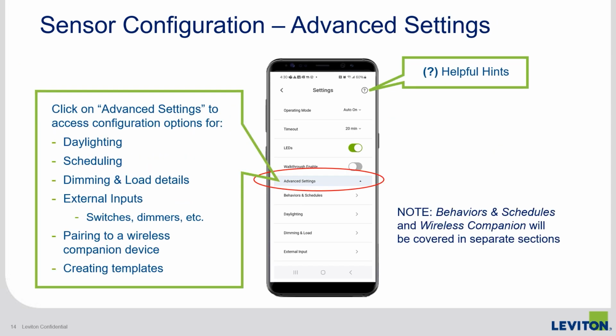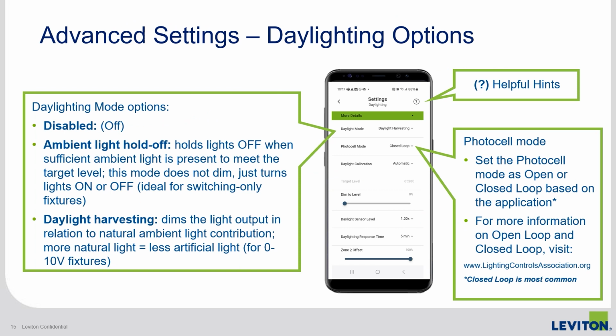Next, we are going to move into some of the advanced settings. In this section, you can program settings for daylighting, scheduling, dimming, and load options. Define external inputs, including the ability to pair with a wireless companion device, and also create templates for spaces that have common settings. Daylight harvesting will raise or lower the light level based on the amount of natural ambient light entering the room or space to meet the target light level. 0 to 10 volt dimming fixtures are required for daylight harvesting.